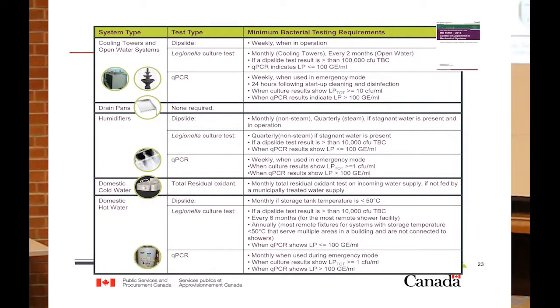Here's a brief summary of the different testing requirements that we have within our standard. If we look at cooling towers, basically it's weekly dip slide testing, so general bacteria levels. Legionella culture testing, minimum once a month, and qPCR testing at system startup, and also following cleaning and disinfections that may have occurred. The reason we do qPCR testing at initial startup is because we can get rapid results.